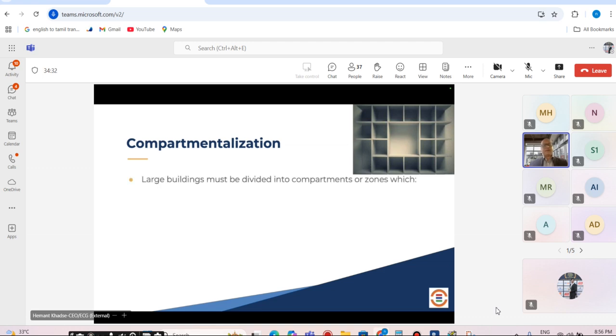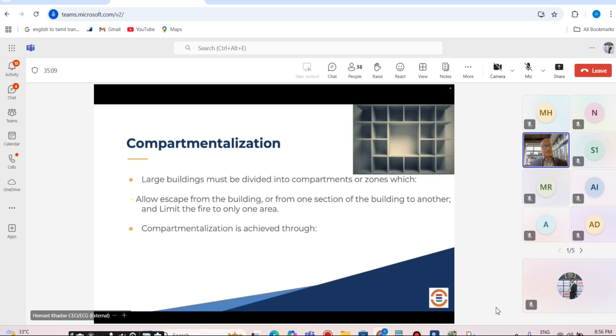There is also another aspect which impacts heavily on life safety, which is compartmentation. Now compartmentation is essentially a principle where we are trying to confine the smoke to a limited space. So it becomes a safe zone for adjoining occupants to either evacuate or defend in place. So when it comes to basements under the building or any large occupancies, compartmentation becomes a very important prevention strategy, and it has been implemented even at code and application level. There are specific areas that have been given and regulated.